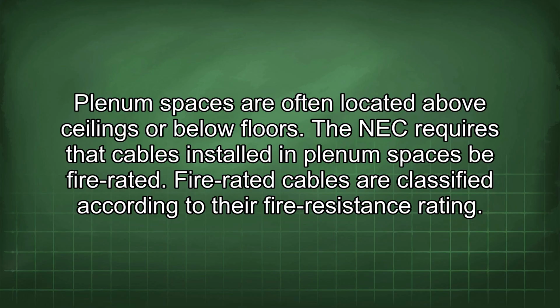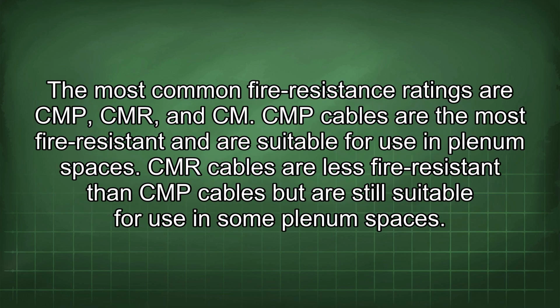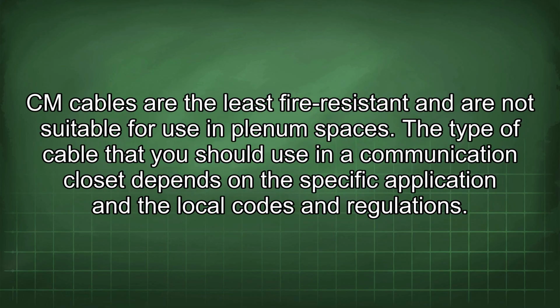Fire-rated cables are classified according to their fire resistance rating. The most common fire resistance ratings are CMP, CMR, and CM. CMP cables are the most fire resistant and are suitable for use in plenum spaces. CMR cables are less fire resistant than CMP cables but are still suitable for use in some plenum spaces. CM cables are the least fire resistant and are not suitable for use in plenum spaces.